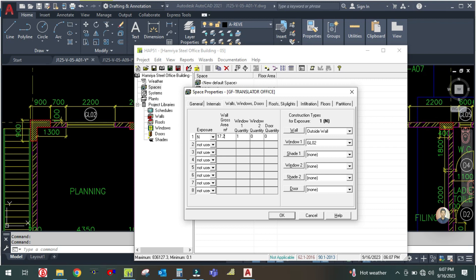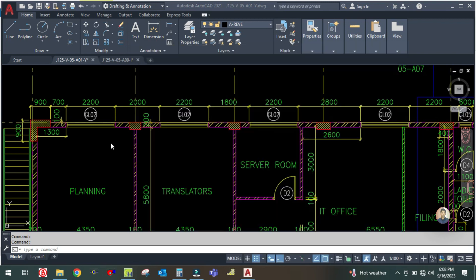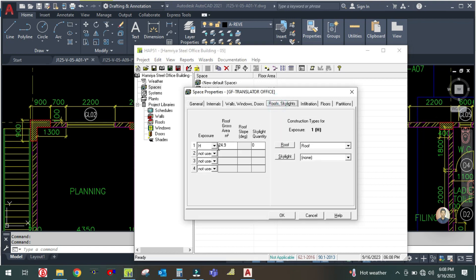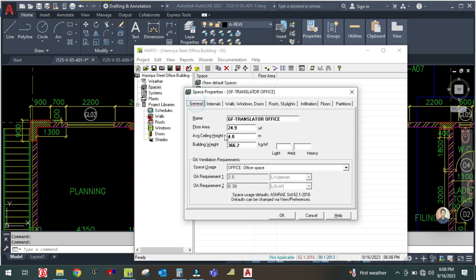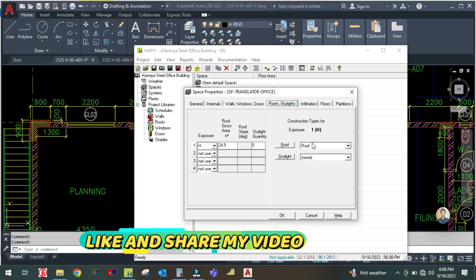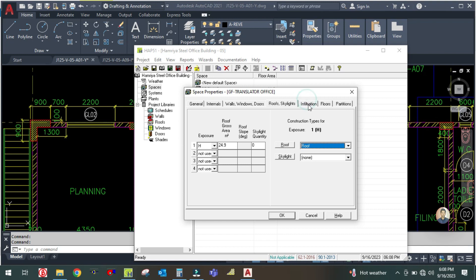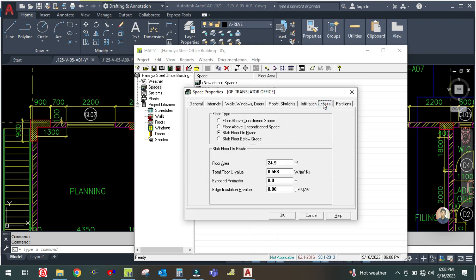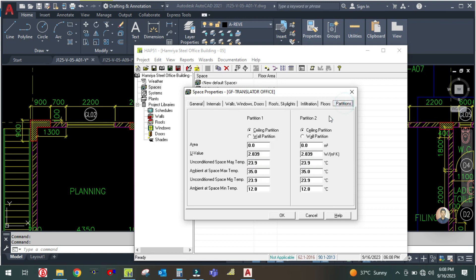Here is the GL2 window. For roof and skylight, select horizontal and the roof area is the same as the floor which is 24.9 square meters. Select the roof type here. Infiltration: there is no infiltration because when the fan is off there is no infiltration. For the floor, it is on the ground floor — slab floor on grade — area is 24.9. There is no partition, so click OK.